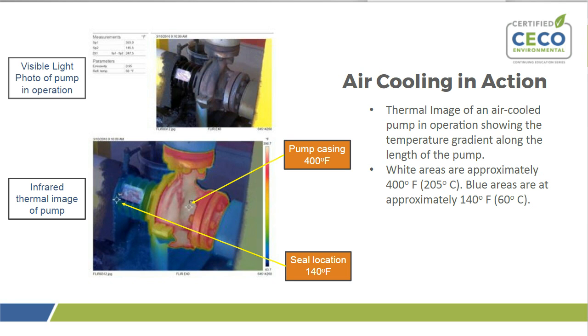Whereas as the temperature goes back, you can see that it drops pretty drastically as it approaches where the seal actually is. The seal location is kept at less than 140 degrees, and all this is due to basically a battle between conduction and convection. The conduction of the fluid and the metal components of the pump wants to push that temperature back to where the seal is, whereas the forced air is pushing convection back and keeping that conduction at bay, basically.